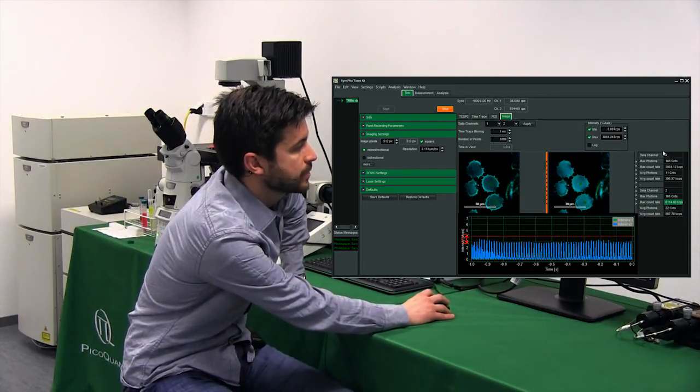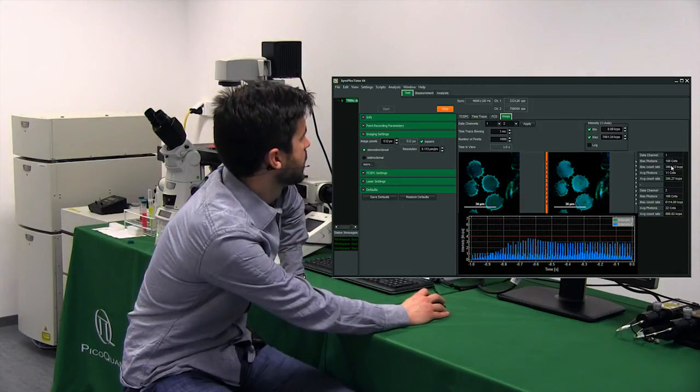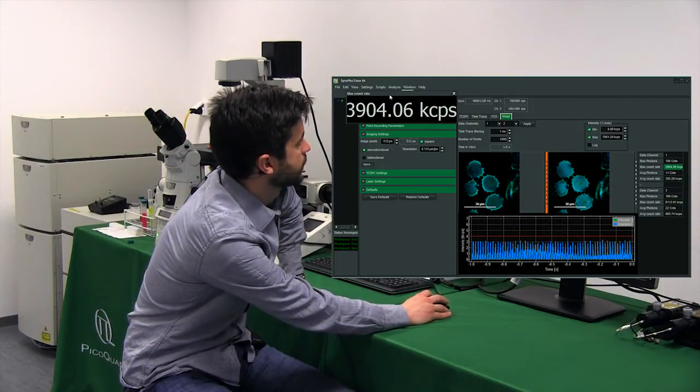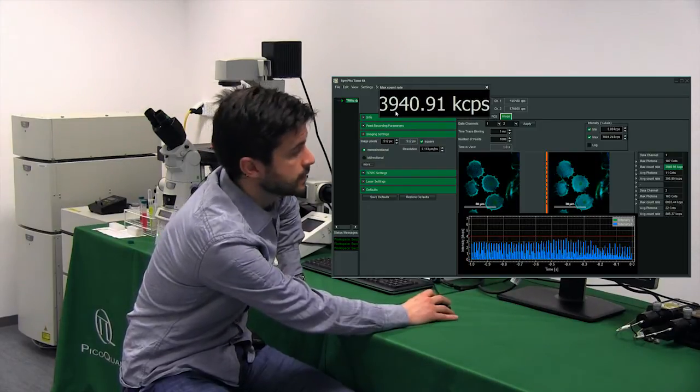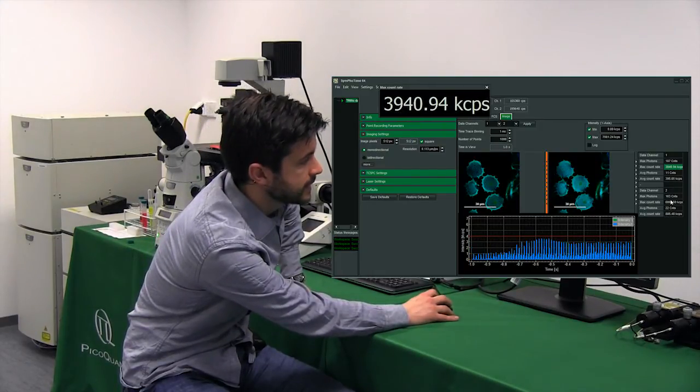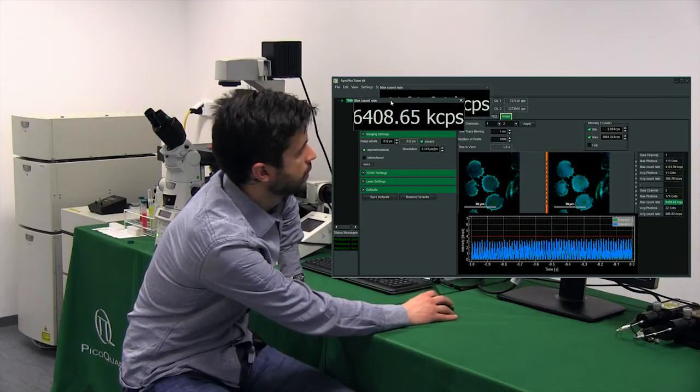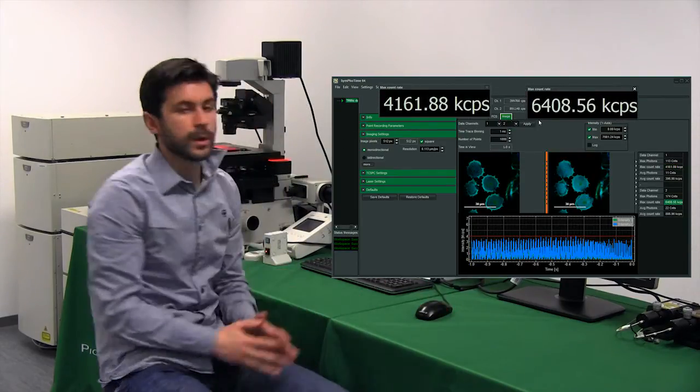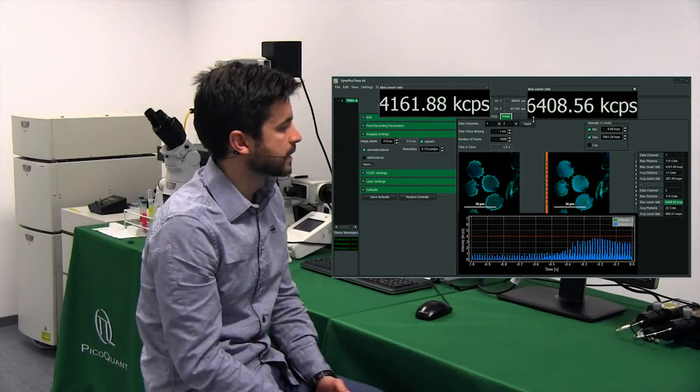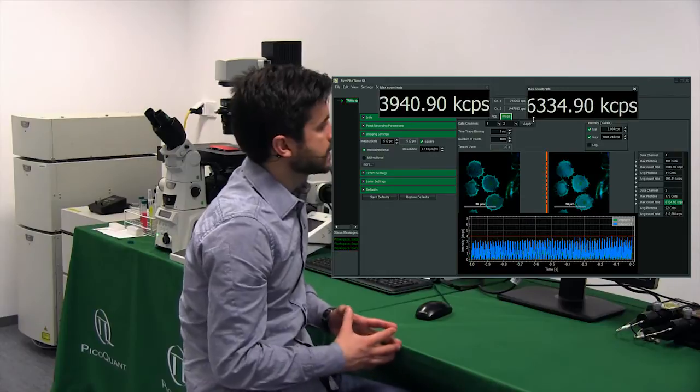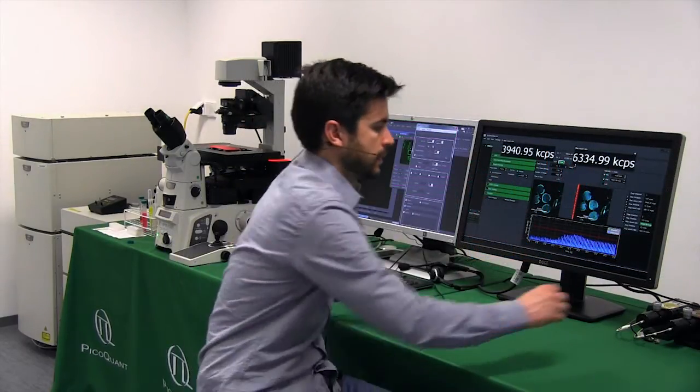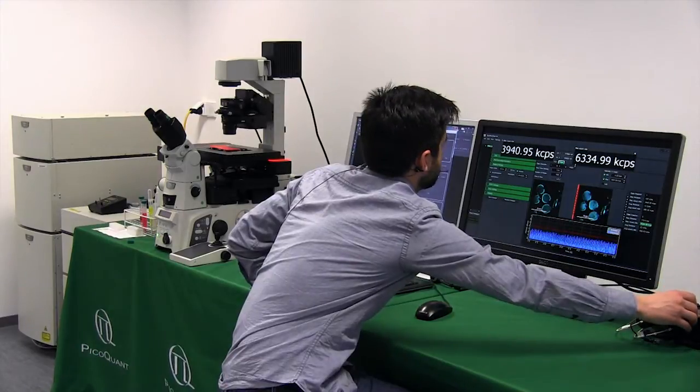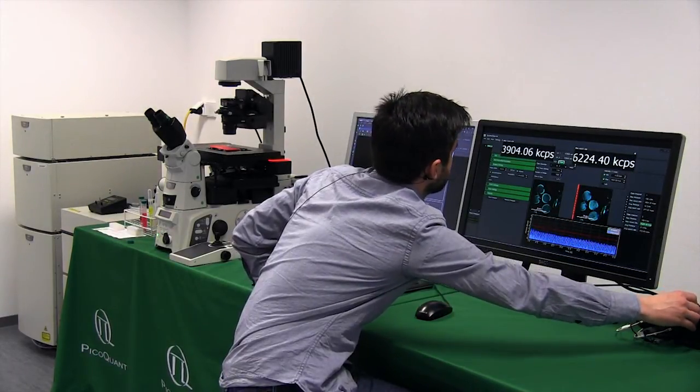To really be accurate and to know if we don't want to overcome the pile up in the brightest pixels, we look at these two tabs here. We go to the maximum count rate for channel 1 and we see that we have 4 million counts so really 10%. But if we go to detector number 2, we've got 6 million counts in the brightest pixel so even above this 10%. So what we do now is reduce the intensity to have at least one at 5% and another one a little bit higher. 5% means 2 megacounts.